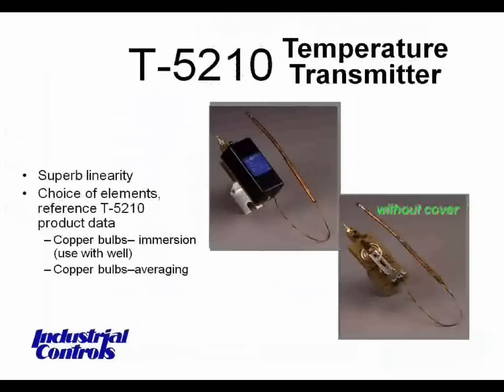Bulb units — this is a T5210 temperature transmitter, and other brands are very similar. Bulb units are small, used in small ducts to monitor air temperature, or used with a well to monitor fluid in a pipe.